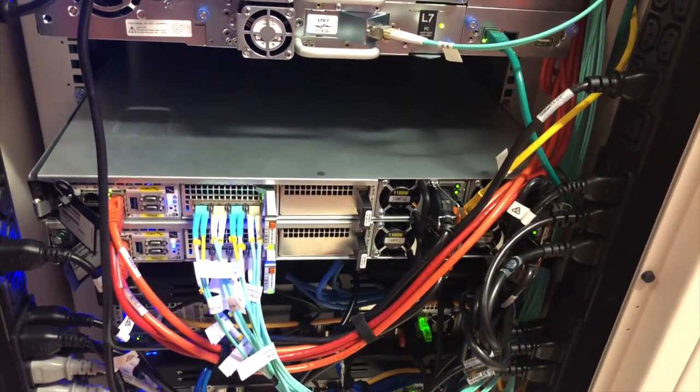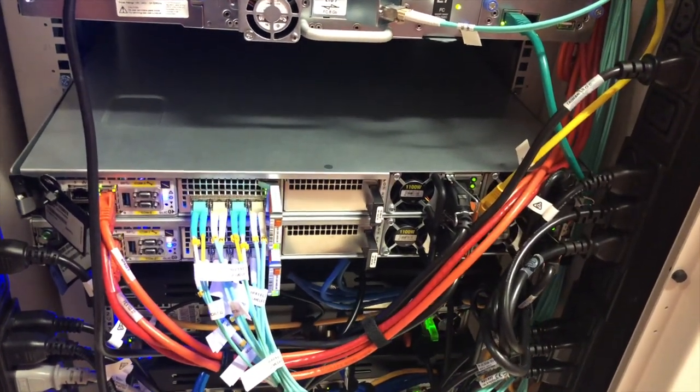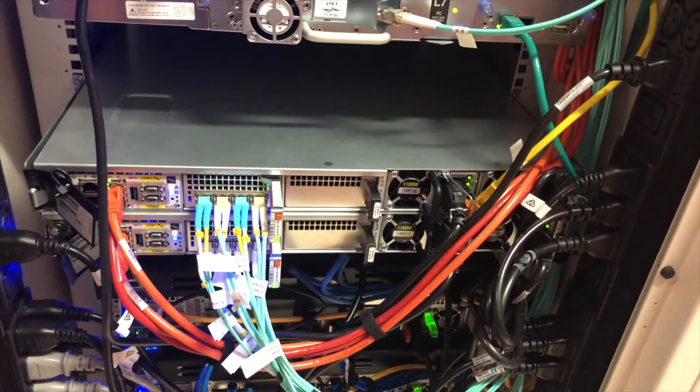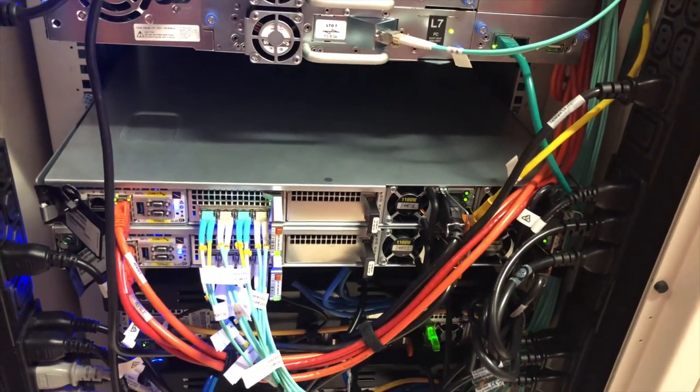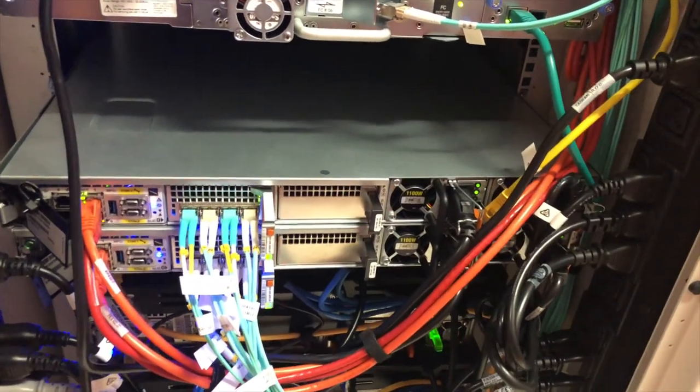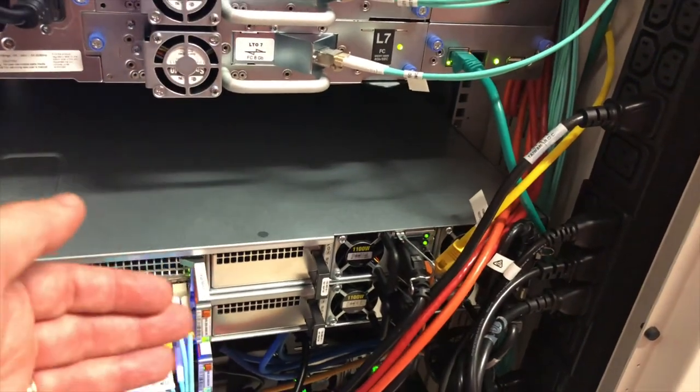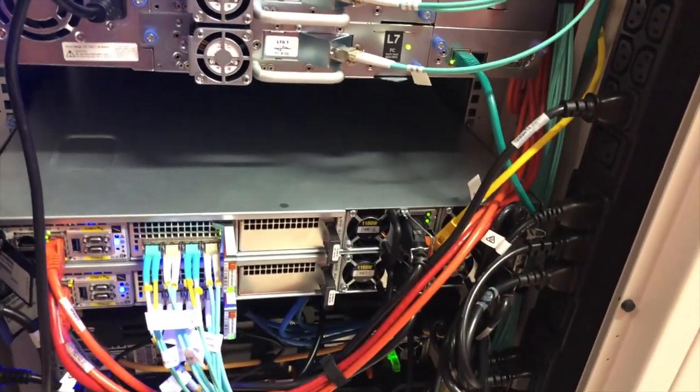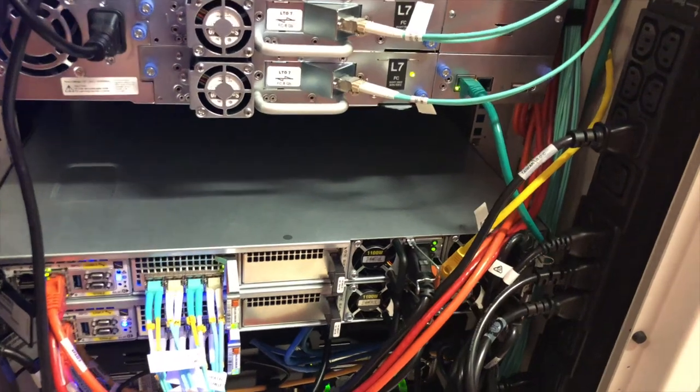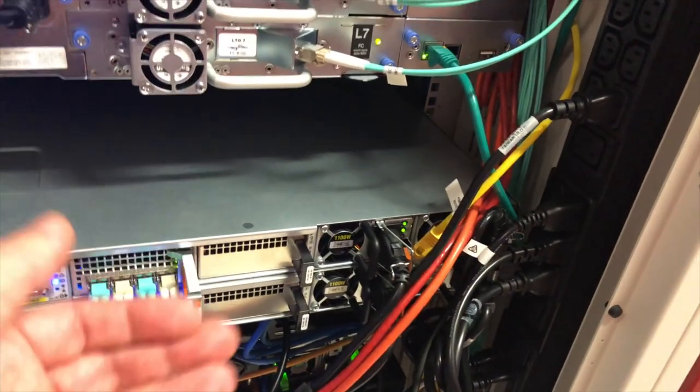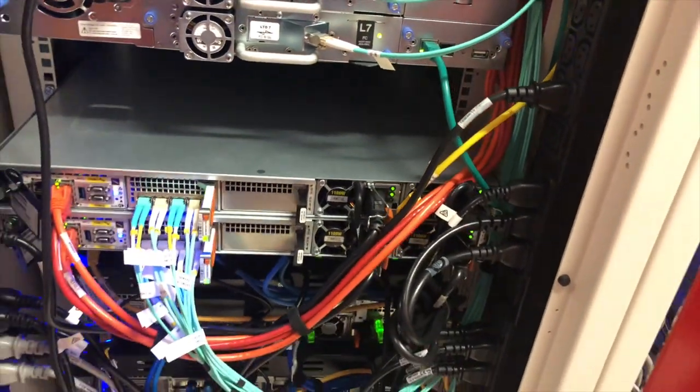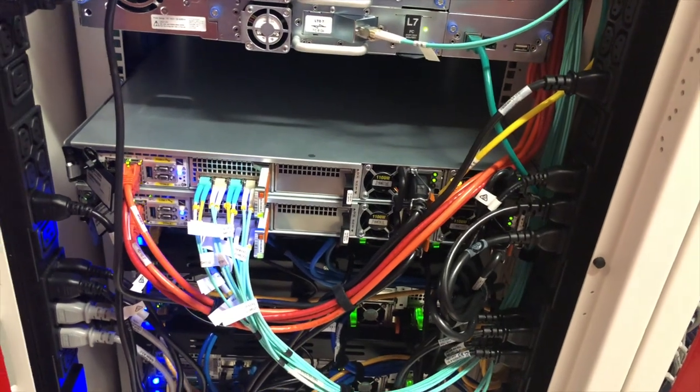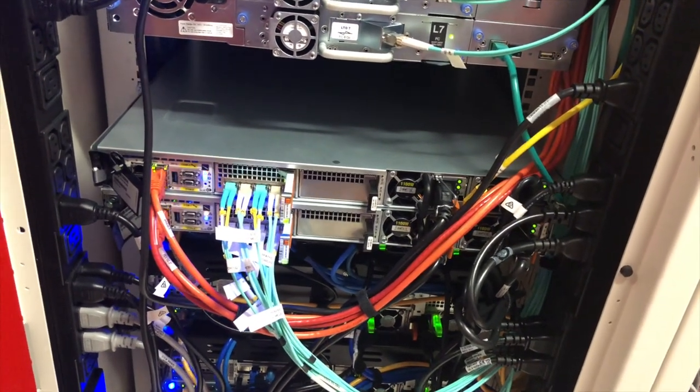Most data centers will have what's called a cold and a hot area. So if you have a fairly large comms room, you'll generally find that the backs of the units will face each other and the fronts of the units will face each other. This is to help with airflow. So in the current place where I'm standing, it's a lot hotter than on the front of the comms room, in front of the data center room.